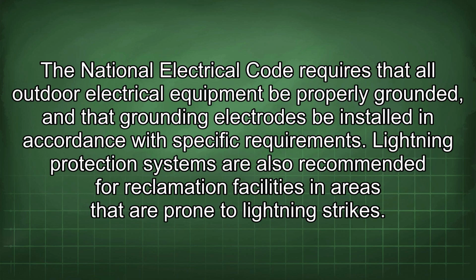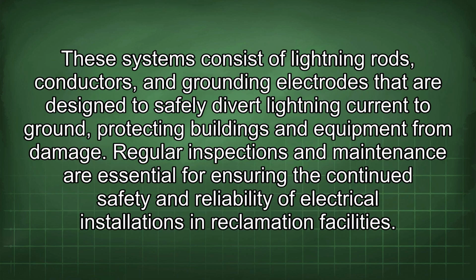The National Electrical Code requires that all outdoor electrical equipment be properly grounded, and that grounding electrodes be installed in accordance with specific requirements. Lightning protection systems are also recommended for reclamation facilities in areas that are prone to lightning strikes. These systems consist of lightning rods, conductors, and grounding electrodes that are designed to safely divert lightning current to ground, protecting buildings and equipment from damage.